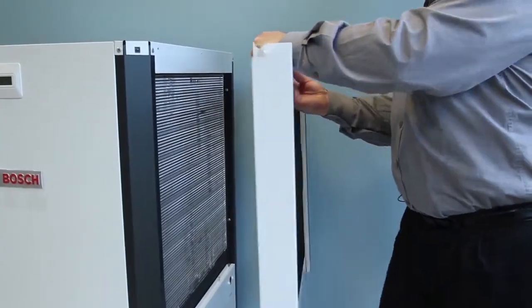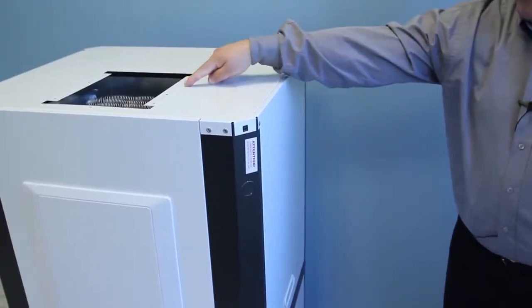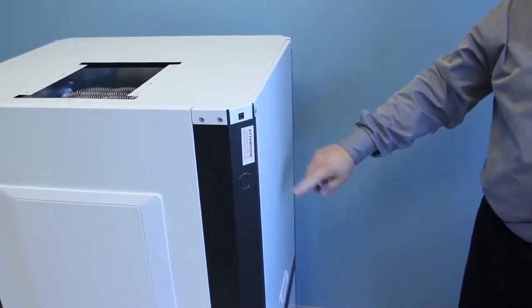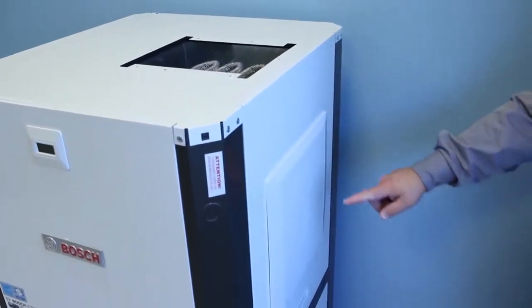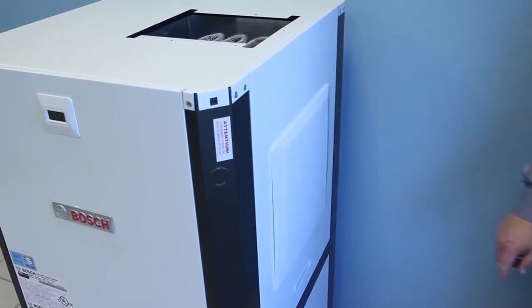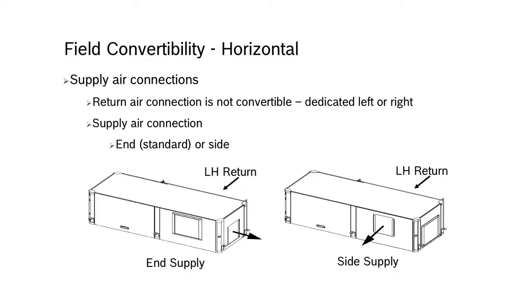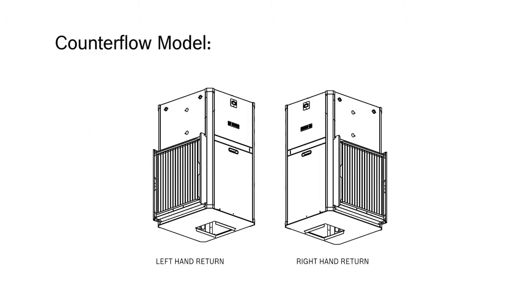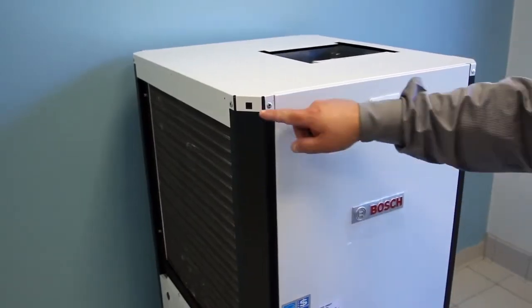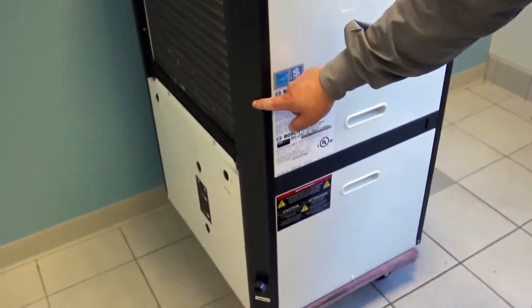It can also be converted from top supply air connection to a back supply air connection or a side supply air connection, which I will also cover in detail. The horizontal units must be ordered either left-hand or right-hand return air connection and is not field convertible. The unit is shipped in the end supply air configuration and can be field converted to side supply air connection. The counterflow models are dedicated left or right-hand return air connection and bottom supply air connection and are not field convertible. Other cabinet features include corners that have 45-degree angles.